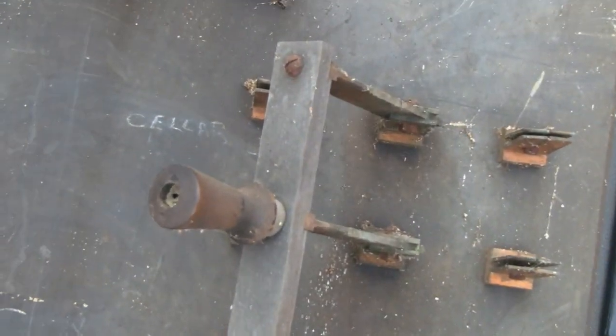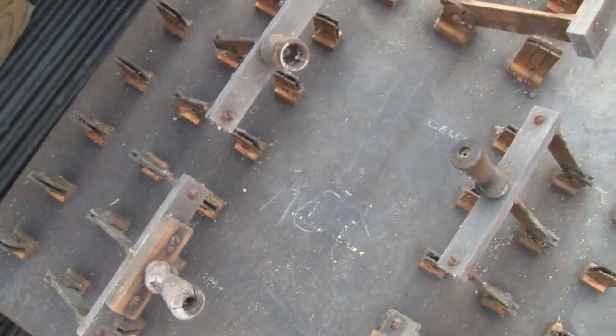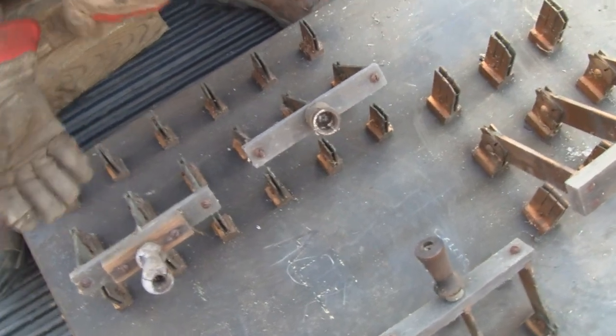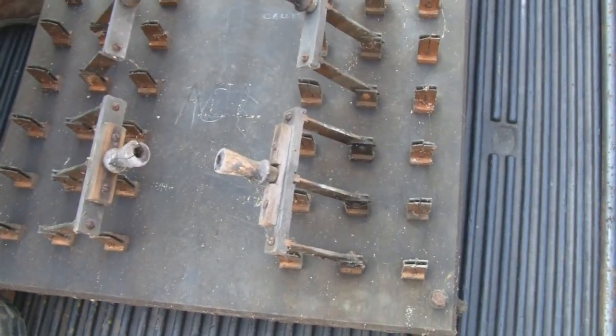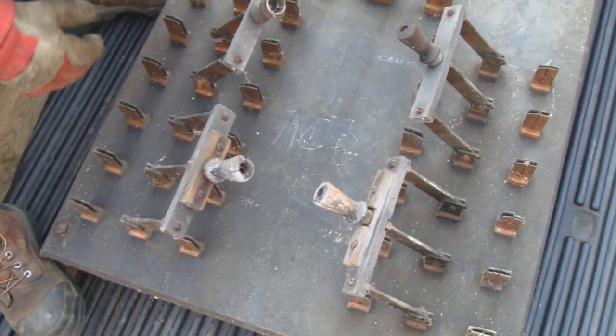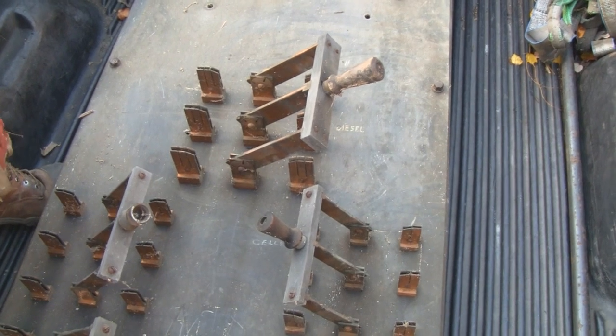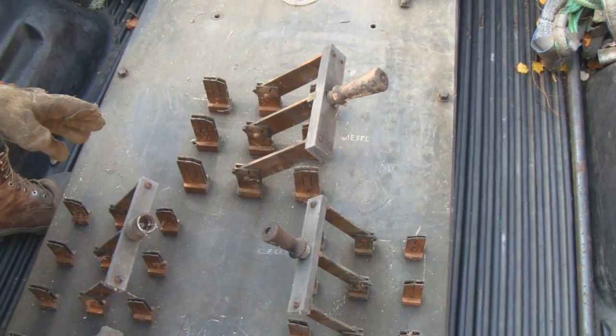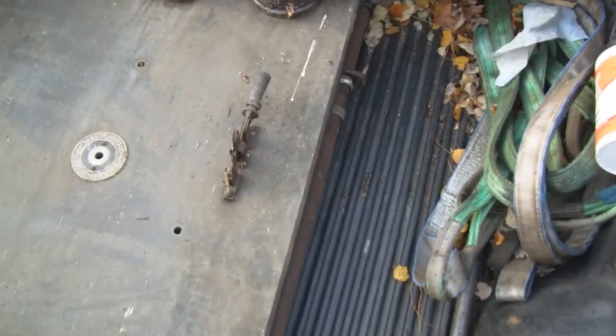Right, so you've got cellar, pump. I would imagine these would be the main loads. So you could have the pump, whatever pump that was. You could either have the pump on diesel or utility, or vice versa, or something along those lines. I don't know yet. Once I flip it over and look at how the bus bars are set up, I could probably trace it out and figure out what on earth they were trying to do here.